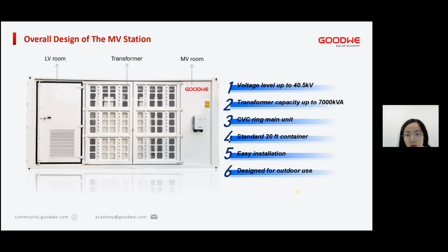We also use CVC ring main units. The size of the MV station is specially designed to be a standard 20 feet container, so it is more convenient for shipment. It also has very easy installation features, and the protection level is designed for outdoor use.